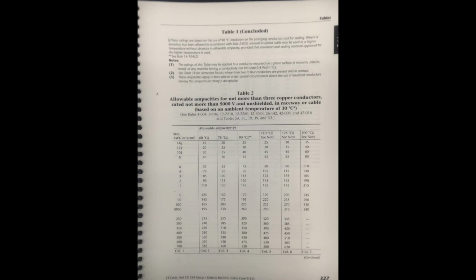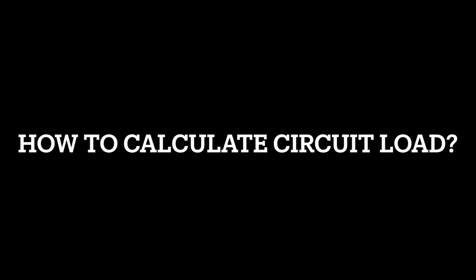So 15 amps. But keep this in mind. If we anticipate our load to be continuous, then we should not exceed 80% of the available load, or 12 amps. As a general rule of thumb, I think it's a good idea if we limit ourselves to just 80% of the circuit load for an additional level of safety. I don't know if you noticed, but sometimes our circuit loads are measured in amps, and sometimes our loads are measured in watts, so we need a way to convert.